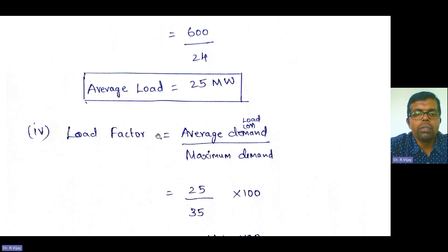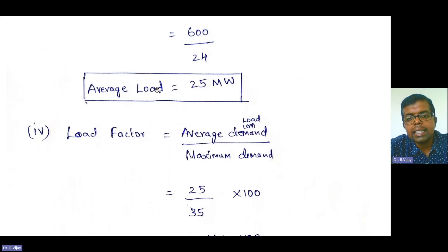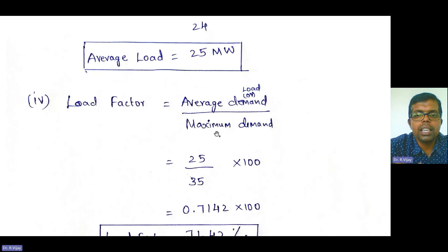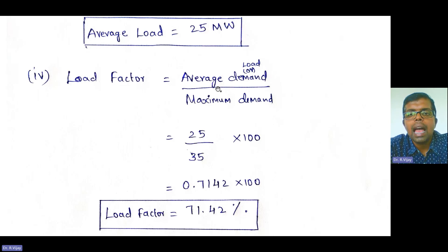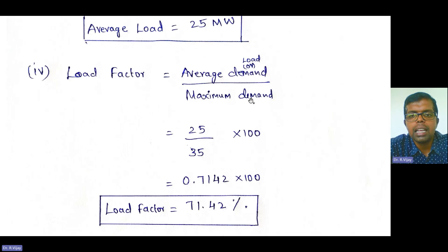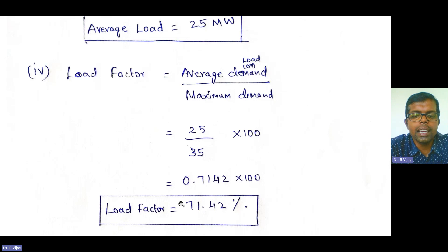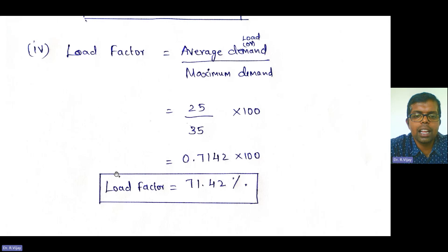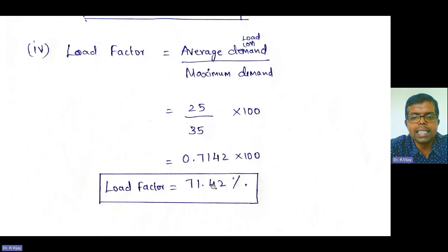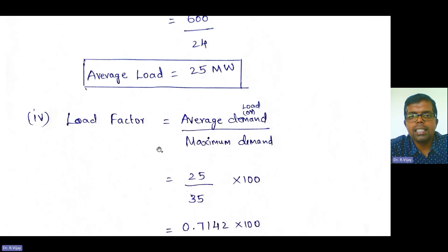Load factor is equal to average demand divided by maximum demand. Average demand is 25 megawatt and maximum demand is 35 megawatt. So 25 divided by 35, multiplied by 100, gives a load factor of 71.42%. Load factor is always expressed as a percentage, and this tells us how efficiently the load is utilized in this particular cycle.